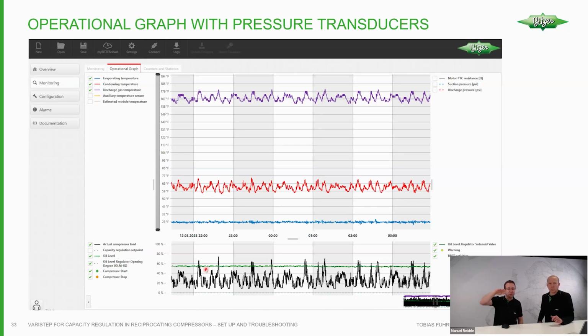Of course, the condensing or high pressure is going a little bit up and down, because the condenser or gas cooler is charged with more or less capacity. This part of the system also has to react to it. But once this is made, you can have a system that is close to running with a flat signal. This is quite good.